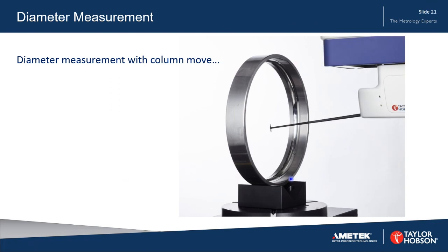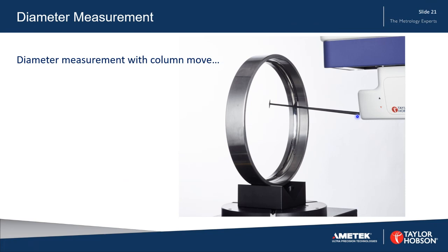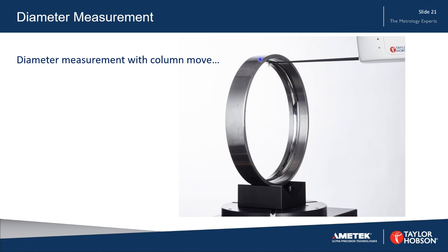We've now moved up, and what we've done is moved the gauge into reverse bias mode. So we're dealing with this tip here, and then we move into contact with the bearing again. And again, we're near the center of the gauge range. But notice that the column has moved on the right here through some considerable distance on this large bearing.